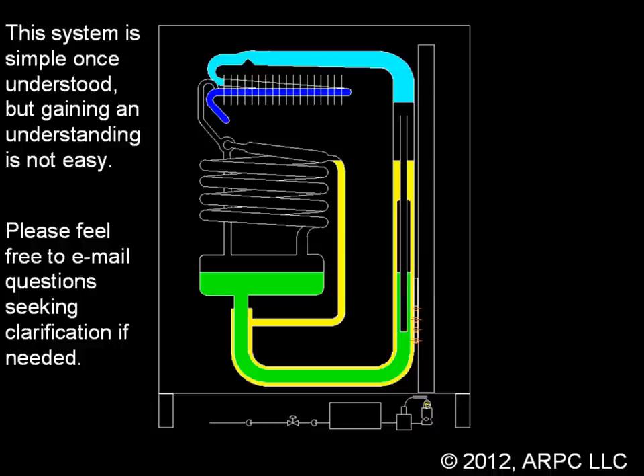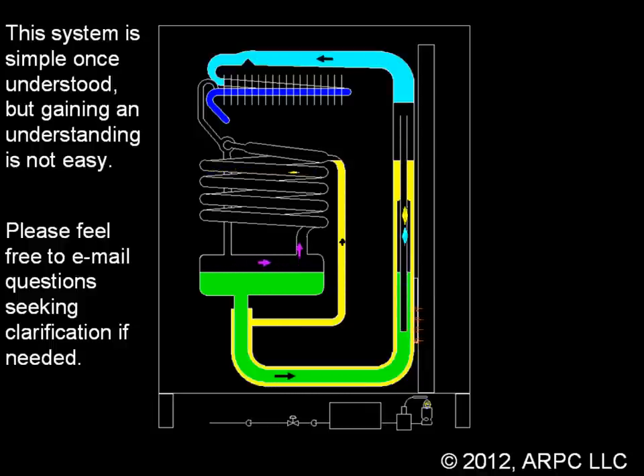The gas flame puts heat into the boiler. The result is for the ammonia to boil, which starts the flow of the refrigerant. At the top of the pump tube, the ammonia gas rises to the condenser, while the weak solution goes down to the absorber coil. The weak solution in the absorber coil reabsorbs the ammonia gas, which reconstitutes the refrigerant, so that it may return to the boiler for another cycle.